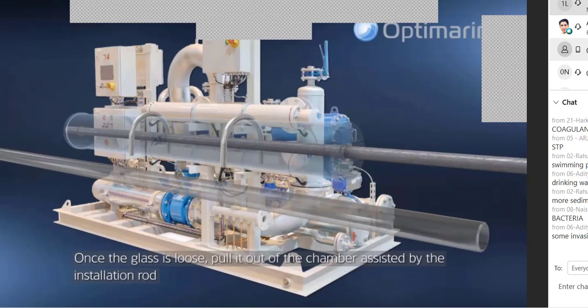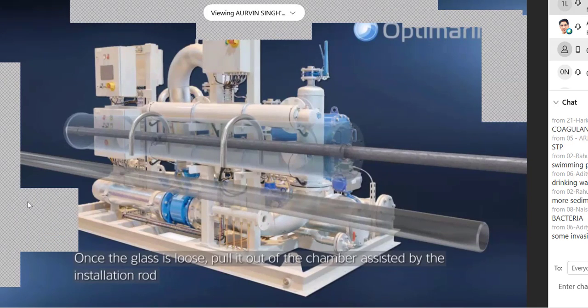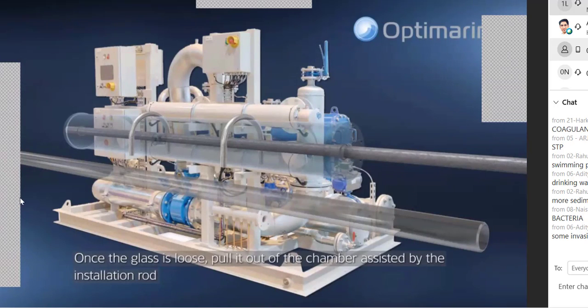Guys, so this is the quartz sleeve here. That is basically protecting the UV lamp that is inside the sleeve. So what happens is that the water is flowing over this, and water will leave some deposits, some yellowish tint on this. Sometimes it is not visible to the naked eye. Now this tint is basically what reduces the effectiveness of the UV system.